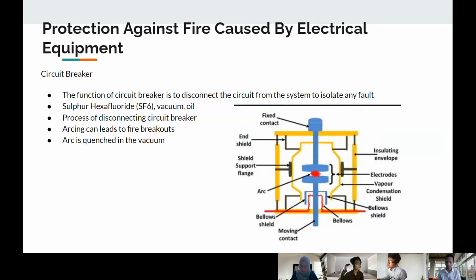When dealing with an electrical system, there will be a risk of getting a fault in the system. In order to isolate the fault, the faulty section must be disconnected from the system. This process may lead to arcing or sparking, which can lead to fire breakouts. When the contact of the circuit breaker is disconnected from the live part of the system, there will be arcing since the jumping of electrons occurs. This arc needs to be extinguished immediately in order to prevent fire.